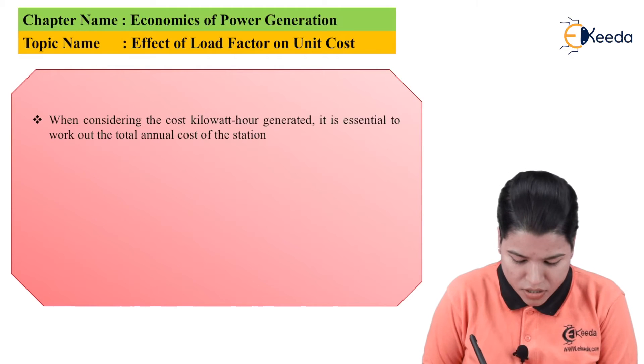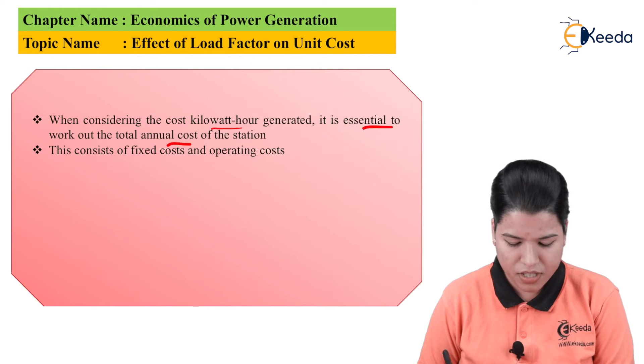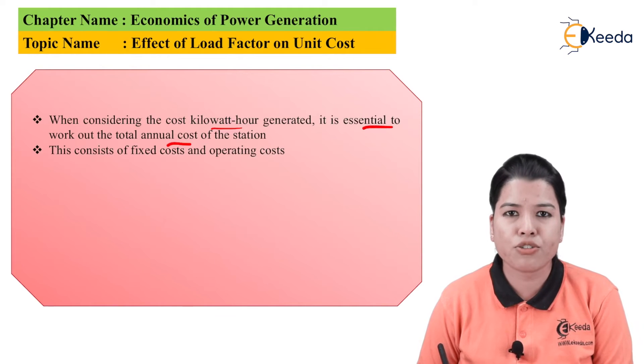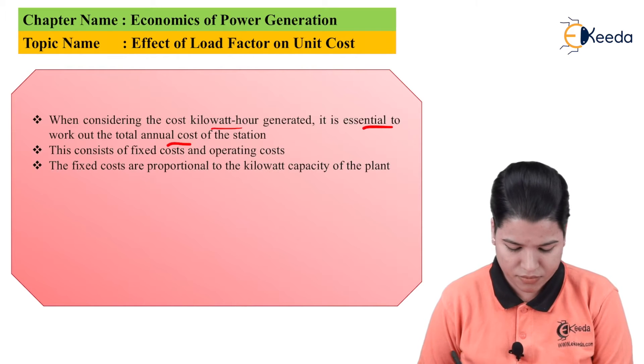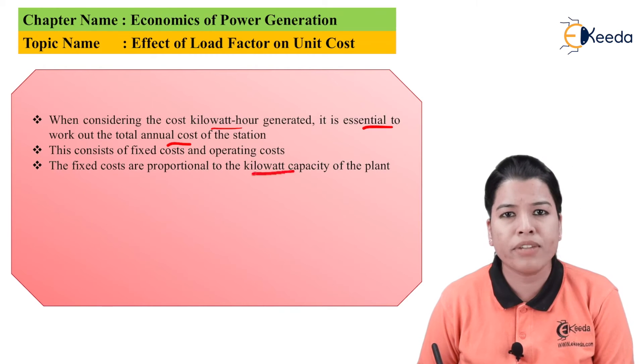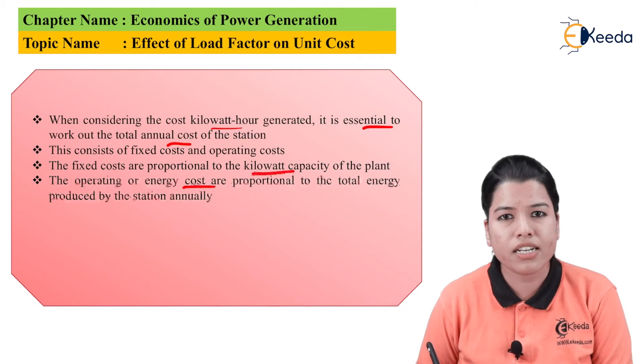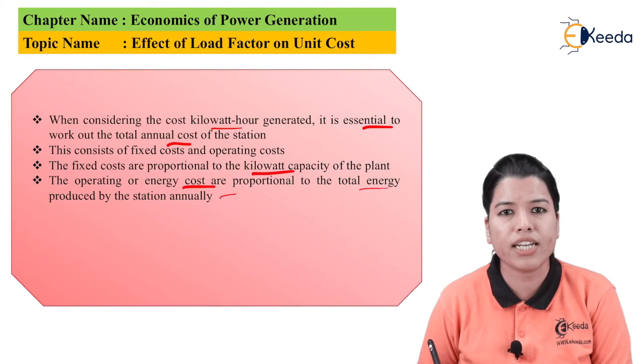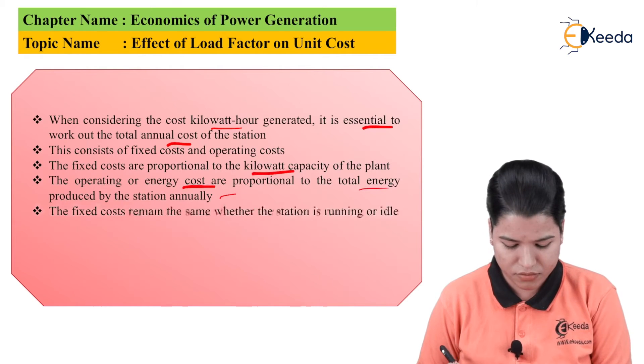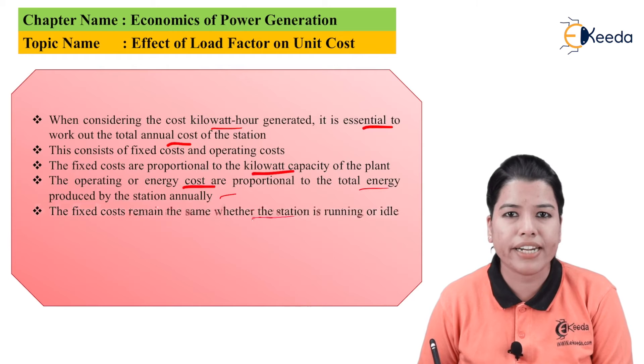Now while considering the cost per kilowatt-hour generated, it is essential to work out the total annual cost of a particular station. This consists of two costs: one is the fixed cost and the second is the variable cost. The fixed costs are generally proportional to the kilowatt capacity of that particular plant. Operating or energy costs are considered to be proportional to the total energy produced by the station annually. The fixed cost will remain fixed whether the station is working or it is in the idle condition.